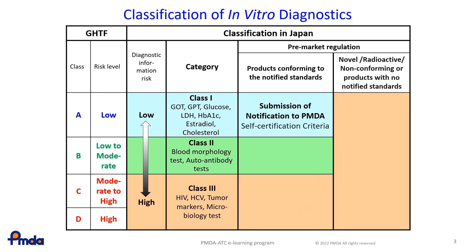IVDs in Japan are divided into three classes. The classes are graded 1, 2 and 3 in order from the lowest to the highest risk. Most of the Class II IVDs can be marketed if their conformity to the requirements is confirmed by an RCB.